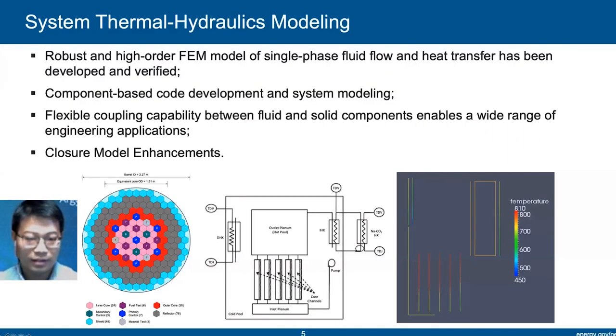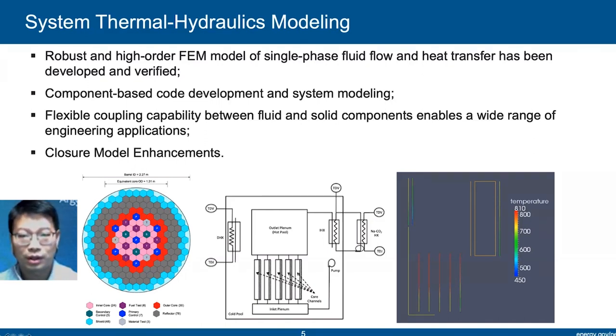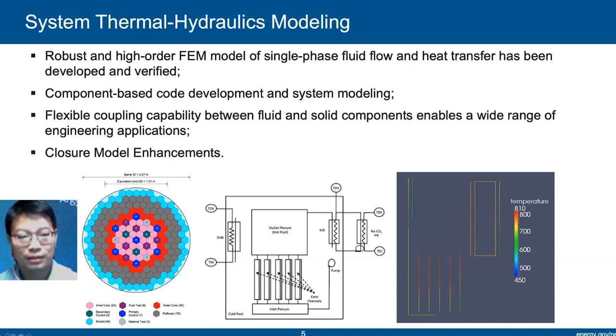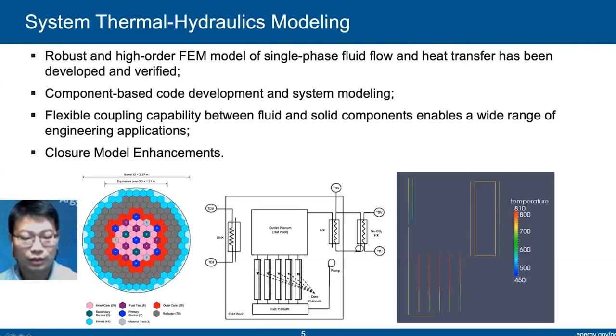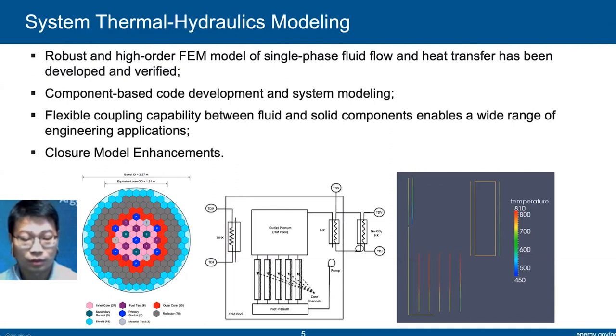The system thermohydraulic simulation models the system using 1D, with high-order numerical schemes providing both accuracy and efficiency. The code is fairly flexible — users can employ basic components to build very complex engineering systems including reactor systems. Integration between fluid and solid components is flexible and covers almost all engineering components for reactor simulations. It has many built-in closure models and allows flexibility for users to provide their own models in input, as well as for fluid properties.